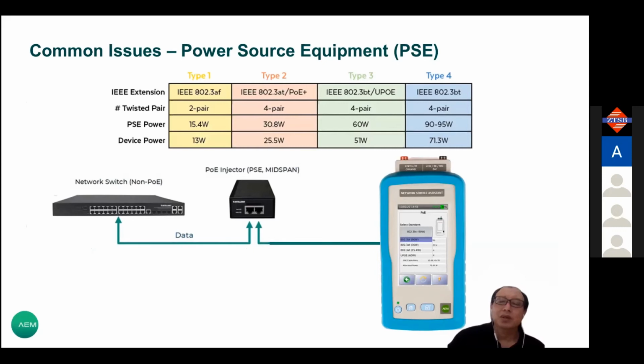Let's talk about the common issues you face in PoE. One issue is that when you have a power source equipment, whether it's an endspan or a midspan, you usually base it on the requirement or spec when you buy the equipment - either a 15-watt supply or a 90-watt supply. Even if you buy a 15-watt supply, at the end of the cable you will not get exactly 100% power, because of the DCR and the cable length there will be some losses. This kind of loss is acceptable.